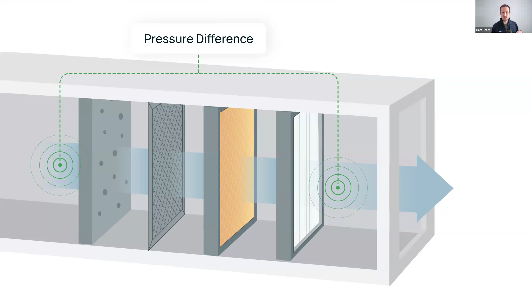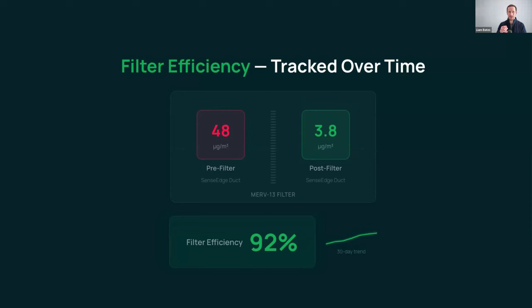Some people here are probably thinking, I already have differential pressure in my BMS, why do I need this? Yes, many BMSs do have a differential pressure reading across a filter, or an alarm that triggers at a certain threshold. But here's the difference: a BMS is designed for automation and alerting, and it excels at that. It is not designed to measure long-term data trends across millions, potentially billions, of data points over multiple months and multiple seasons. But that's exactly what you need when looking at filter performance, because this doesn't happen overnight. If you want to understand true performance over time, this is a much longer process.